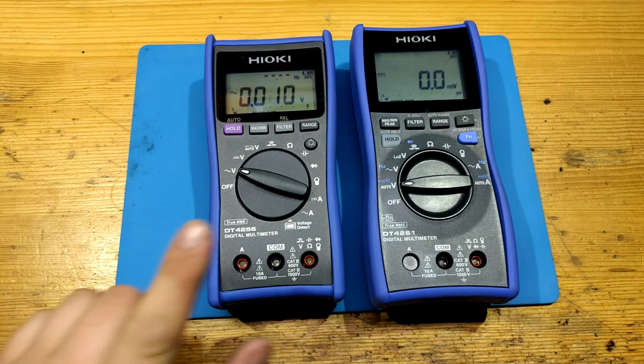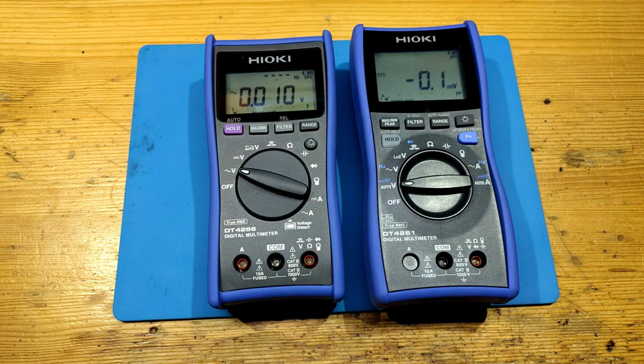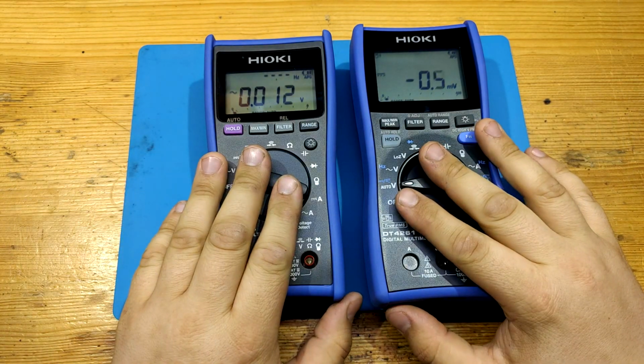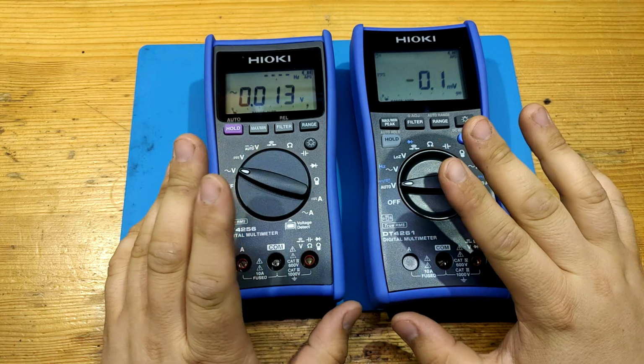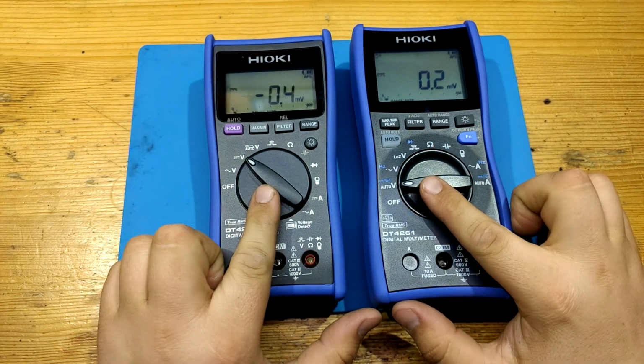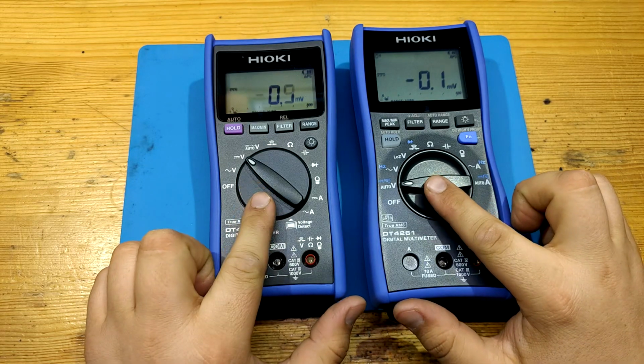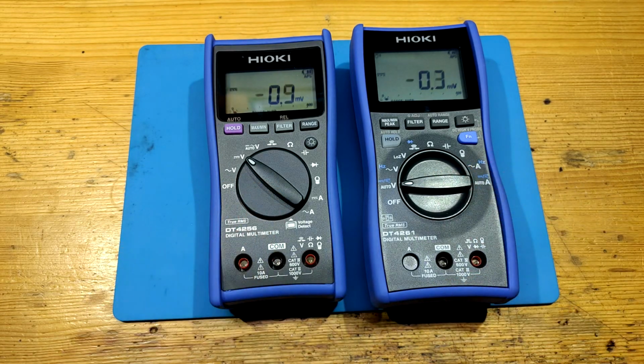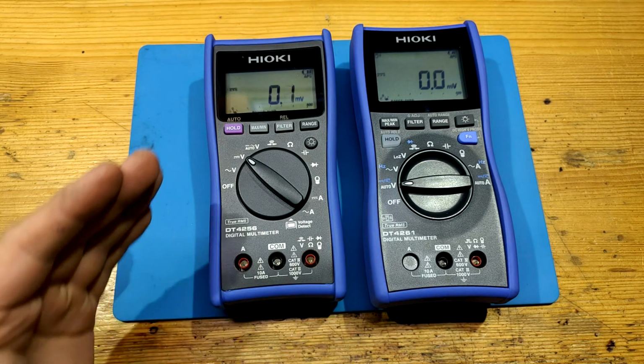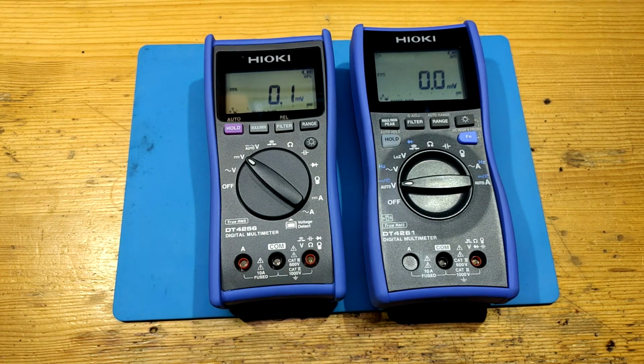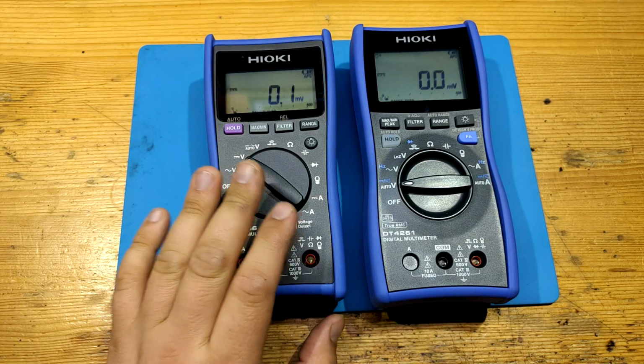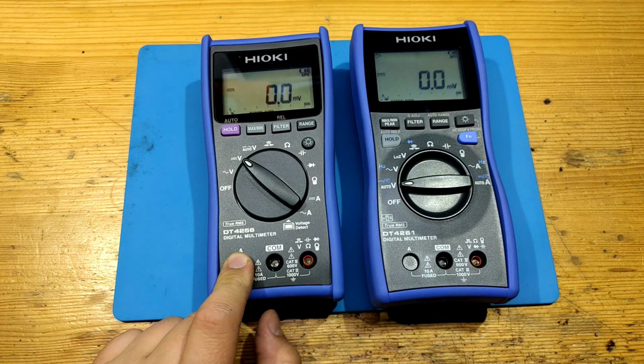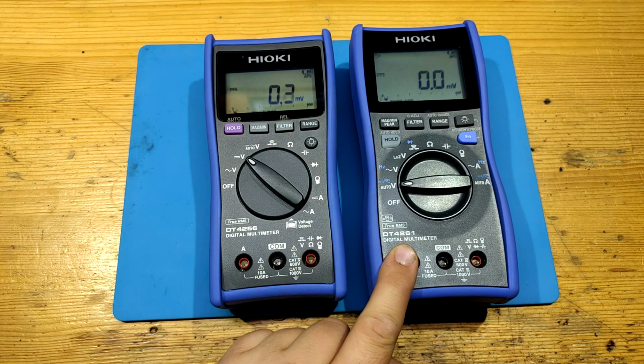The low pass filter is great as it blocks higher frequencies that may be caused by frequency converters or switched mode power supplies on the line. Now the funny part. I checked for the accuracy on my 10 volts DC reference. Both of them said 10.00. These DMMs have a more accurate ADC than what their display can show. They are also very far away from nominal 0.3 accuracy for DT4256 or 0.15 for DT4261.